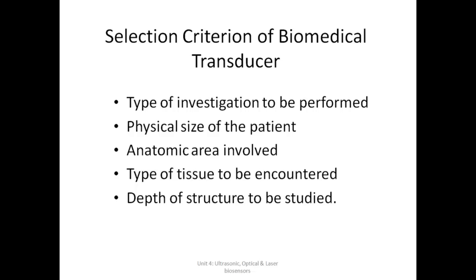Firstly, the type of investigation that is to be performed: is it imaging, is it diagnostic, is it therapeutic? What kind of investigation we need to perform has to be thought of. The physical size of the patient matters, of course, because for a child it will be something else, for an adult it will be something else. If there is an obese patient, the probe that we have to use will be of different specifications. Then the anatomic area involved: if the eye is involved, for example, then you need a much safer instrument, but if you're putting it on the skin, you might be using a normal transducer. So which kind of anatomic area is involved has to be thought of. The type of tissue that is to be encountered is, of course, important.